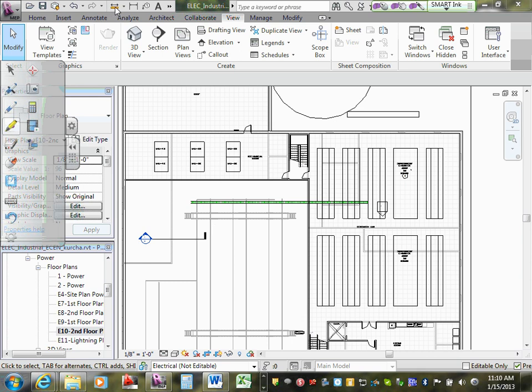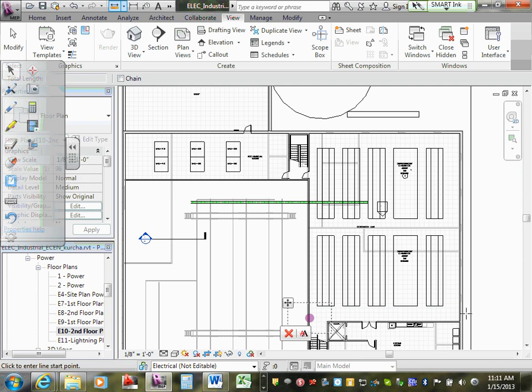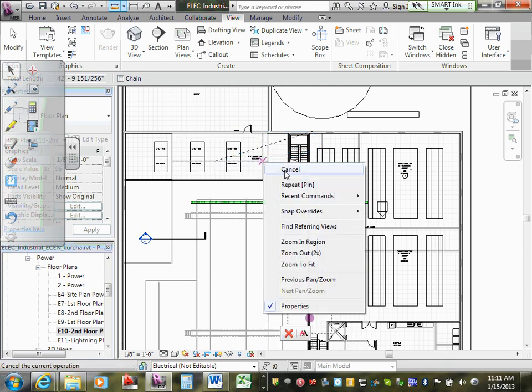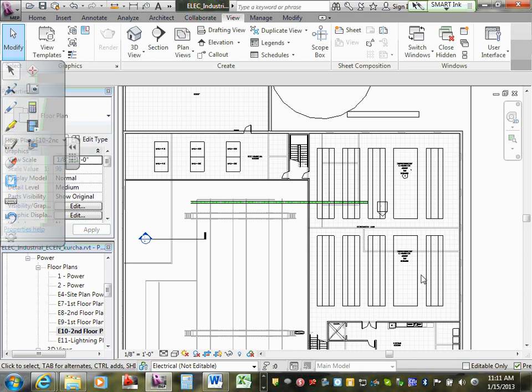So you have a smoke detector every 30 feet, so 15 feet out, and then every 30 feet there. Now designing, the first smoke detector is going to be out here. Here's your first smoke detector. The second one is 30. So on and so forth. That will give you your design layout for smoke detectors in a regular area.